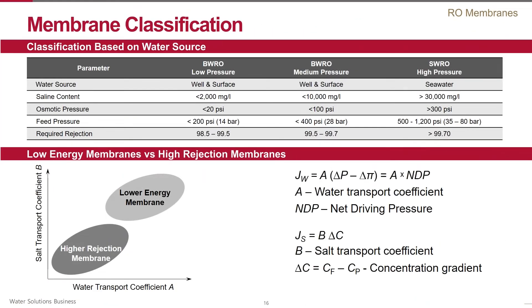There are several ways to classify RO membranes. One of them, shown here, depends on the water source of the application. In general, membranes can be divided into seawater and brackish water membranes depending on feed water salinity. Here in the table you can see very approximate brackets for each membrane. For example, for seawater membranes, the salinity varies from 30,000 to 35,000 milligrams per liter and up, and these membranes can operate at pressures up to 80 bars.